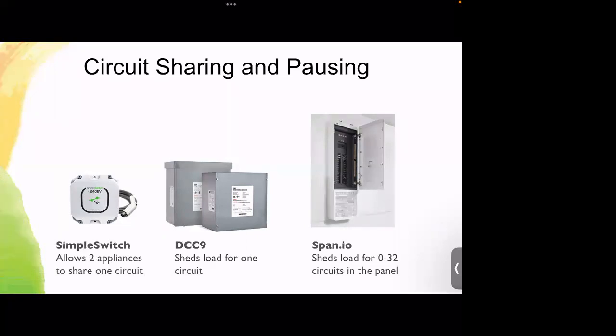The device on the right is something called a smart panel, made by a company called span.io. Instead of working at the single circuit level, the smart panel does this for all the circuits in the home. It has intelligence, and you pre-program it to say, if my panel starts to reach capacity, first cut off the EV, then maybe cut off something incidental in your home, like the dryer. I don't know what it would be, but it sheds each load according to a pre-programmed list that you give it.